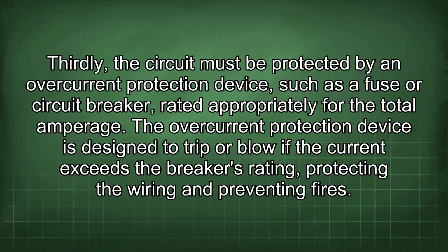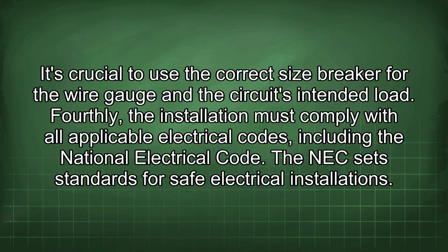Thirdly, the circuit must be protected by an overcurrent protection device, such as a fuse or circuit breaker, rated appropriately for the total amperage. The overcurrent protection device is designed to trip or blow if the current exceeds the breaker's rating, protecting the wiring and preventing fires. It's crucial to use the correct size breaker for the wire gauge and the circuit's intended load.